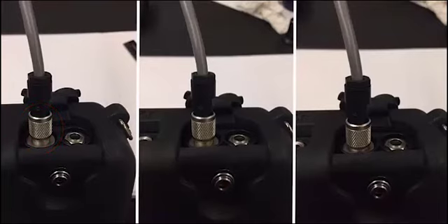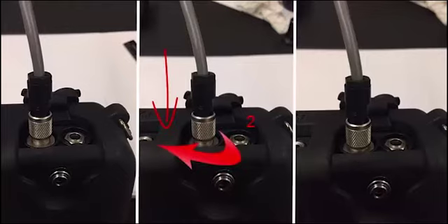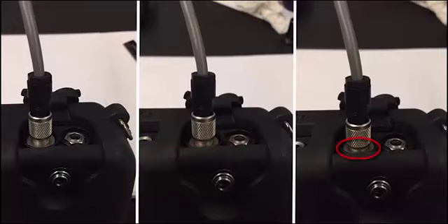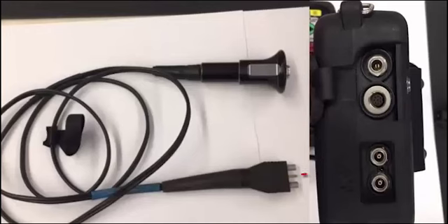Once it is seated properly, you can screw in the cable by applying slight pressure and turning the knurled section of the encoder cable clockwise. Screw in the cable until it is snug. It does not screw in all the way, so some threads will likely be exposed. This is fine. We can then plug the D790-SM transducer cable into the top of the 38DL Plus and turn the instrument on.